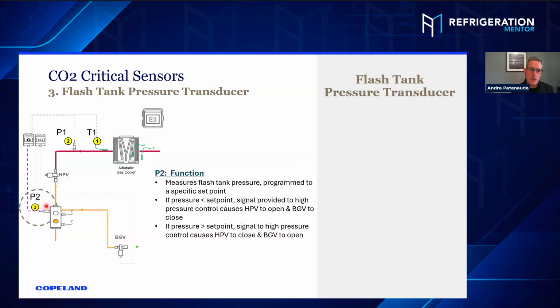P2. That's my flash tank pressure transducer. Now this represents basically a static pressure. P1 is dynamic. It's changing all the time. Yes, this pressure in here changes, but it has a static set point. It measures the flash tank pressure and is programmed to that specific static set point. So if the pressure is lower than the set point, the high pressure valve opens and the bypass valve closes, and the reverse, right? If it's above the set point, this high pressure valve closes and the bypass valve opens to try to maintain it.